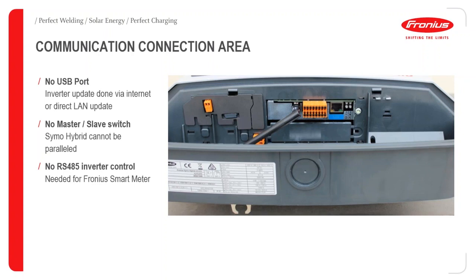Okay, then to the hybrid manager setup. In the inverter itself, if any of you are familiar with the Datamanager, it's a very similar board. We call it the hybrid manager because there are a couple of little differences between this and the Datamanager. There are a lot of similarities, but there's the odd little difference. One of the main things, if you look underneath the hybrid inverter, you'll see the USB slot is covered over with a little cover. That's because the software updates are not done via USB as opposed to the other Snap inverter range.